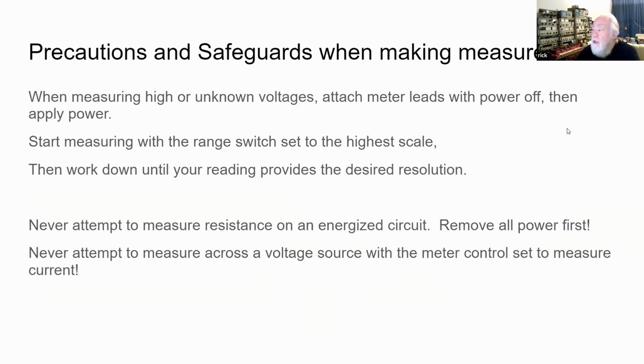So some of the precautions you should take when using the meter is if you're measuring high voltages or unknown voltages, start with the power turned off, attach the meter leads with alligator clips, and then apply the power after setting the meter range switch to the highest scale value, and then move the scale switch down as you determine what the voltage is to get a little bit more resolution.